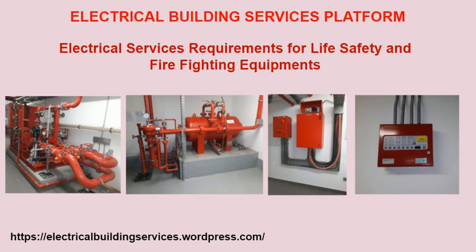Number 20. Whichever secondary power source is provided, the distribution should be organized such that the secondary supply remains live when the remainder of the supply in the building are isolated in an emergency. Number 21. Cables, switchgear, and other equipment transmitting the secondary power supply should be separate from those of the primary supply or be physically protected so that a breakdown or any cause of breakdown on one supply will not lead to the simultaneous failure of the other supply.